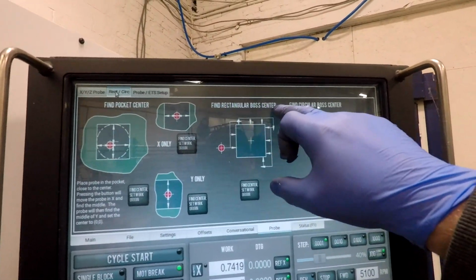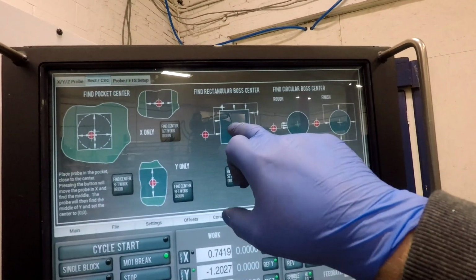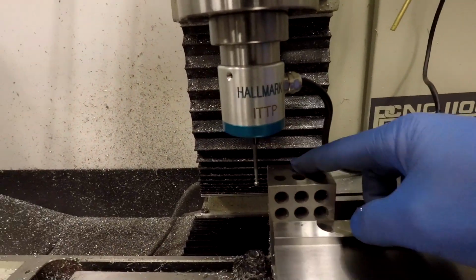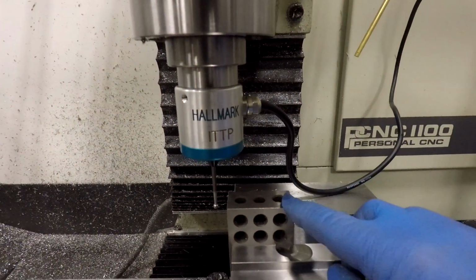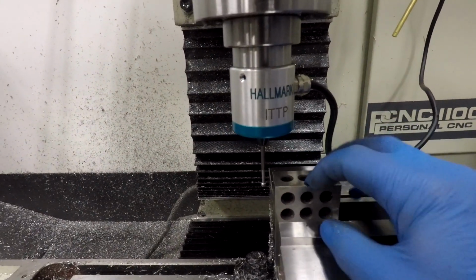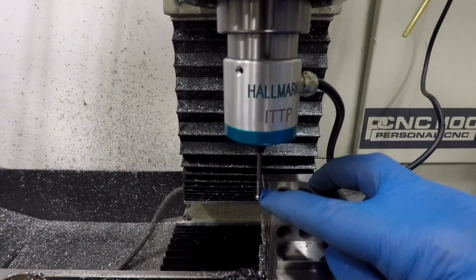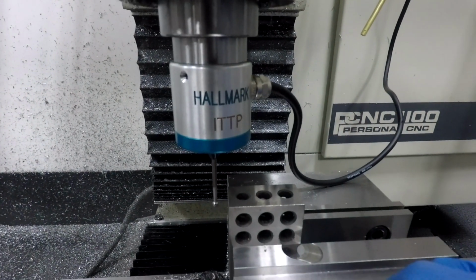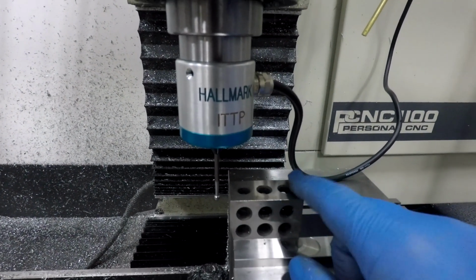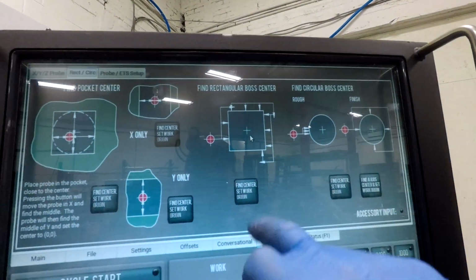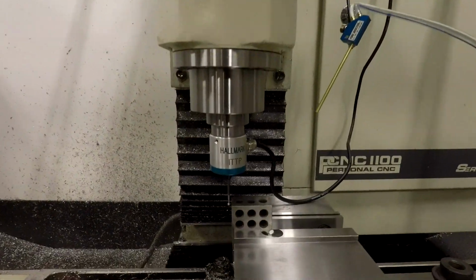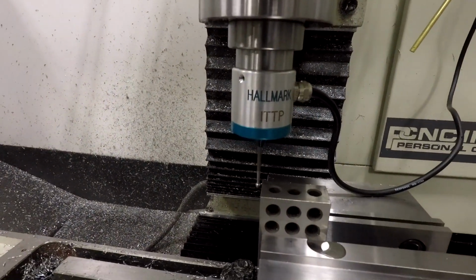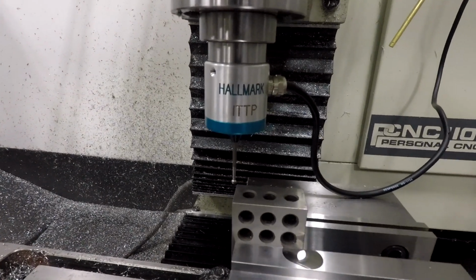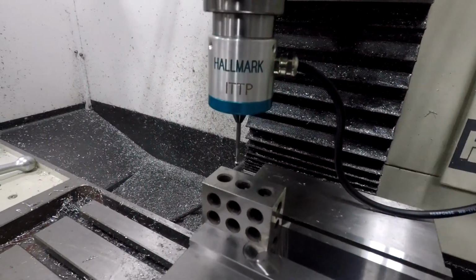Alright, so we're going to do the find rectangle boss center. So we want to find the center of this rectangular shape. And I'm using a 1, 2, 3 block, so we got 1 inch, 2 inch, and it's 3 inch high. But that doesn't matter. We're just going to set the X, Y, and then Z off the top of this. So we're going to use the probe setup first. All we have to do to set the XY0 on this is basically find the center, set work origin. So I just hit that, and this thing will run a routine where it finds the general outline of what kind of shape we're dealing with.